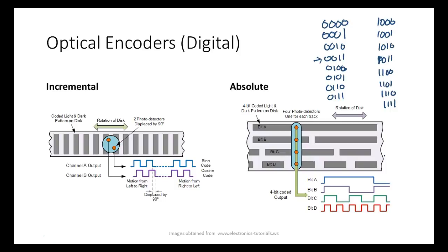So I've got to add more stuff. I've got to add digital counters. Well, PLCs like to do what? They like to count. Unfortunately, the counters in the original PLCs were done by software, by programs. And a lot of times the programs couldn't keep up with the count. So just about all your PLCs now have what they call a high-speed counter, which is actually a hardwired, true counter that's on your PLC. These guys will scream, and they'll be able to handle these encoders.